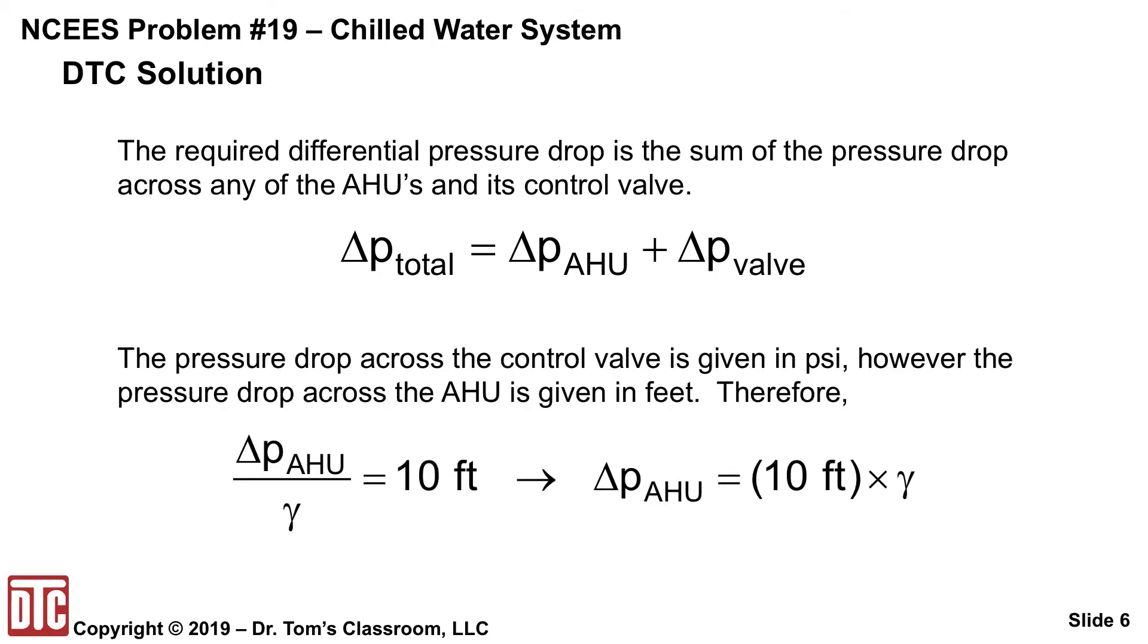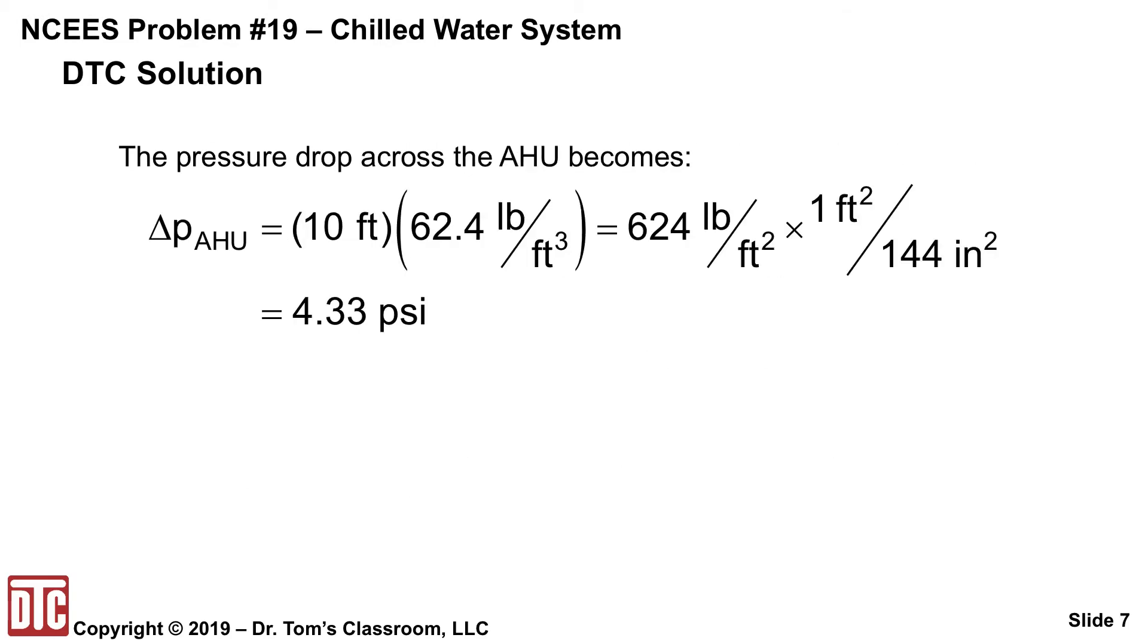So the 10 feet that you're given is delta P of the air handling unit divided by gamma. So you just need to multiply both sides by gamma. So the change in pressure drop across the air handling unit is just 10 feet times gamma. And this is given in 10 feet of water.